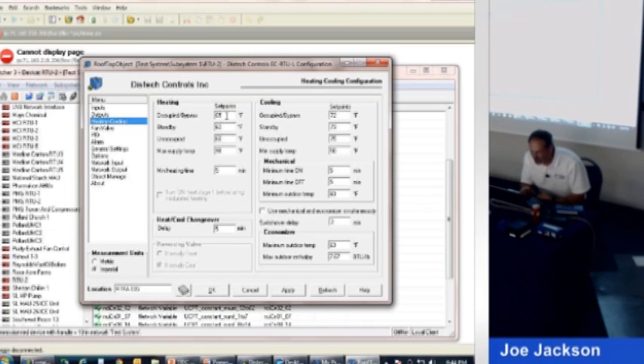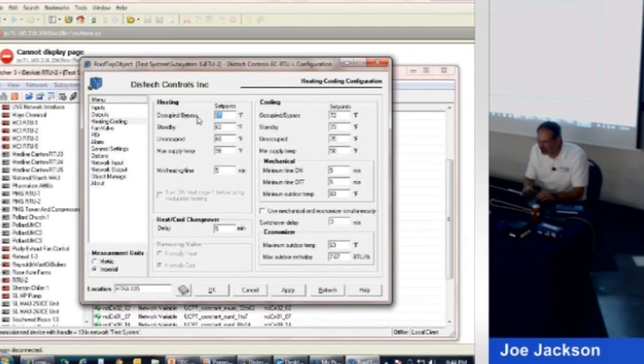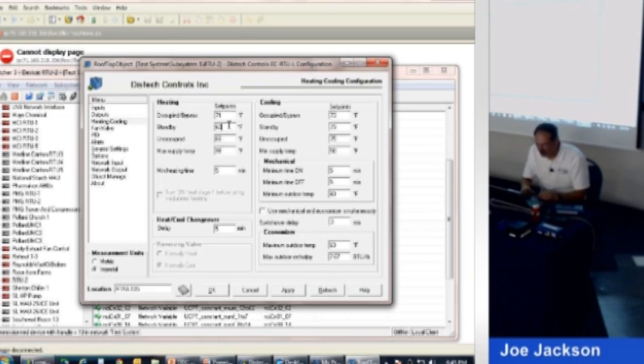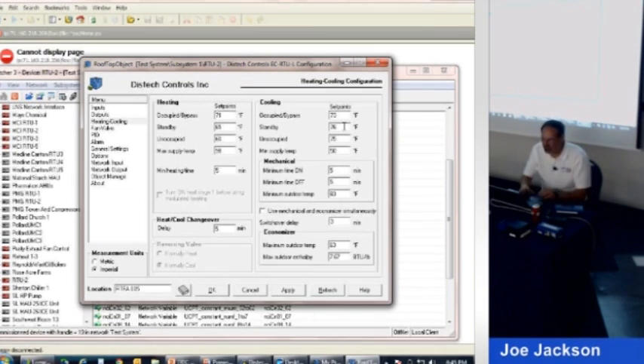But here's the occupied heating, occupied and bypass. Occupied is obviously when the unit's occupied. Bypass is when somebody comes over here and hits this little override button and the thing runs for an extra 2 hours or whatever you decide. So we're going to say the heating is at 71 degrees. And the cooling we'll set at 73 degrees. And standby, this would be like for a school. So occupied is when the kids are all there. Standby is what happens when all the kids and teachers leave, but the custodians are still there. They're not quite as nice to them. They're only going to keep it 65 degrees, and they're going to let the temperature go clear to 76 degrees in the summertime. Then eventually, the custodians finish their job and they go home. The temperature drops to 60 degrees or goes clear up to 80 degrees.